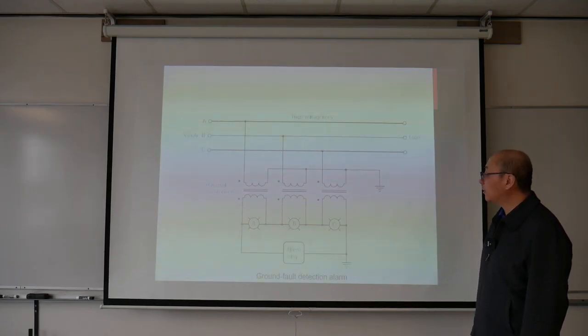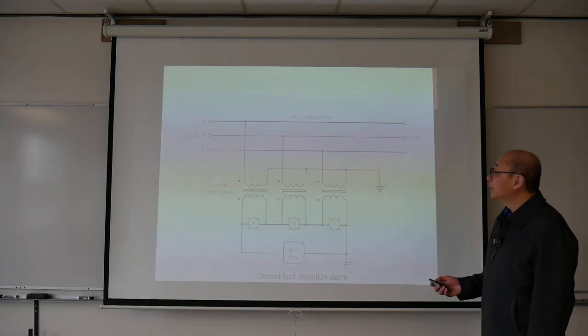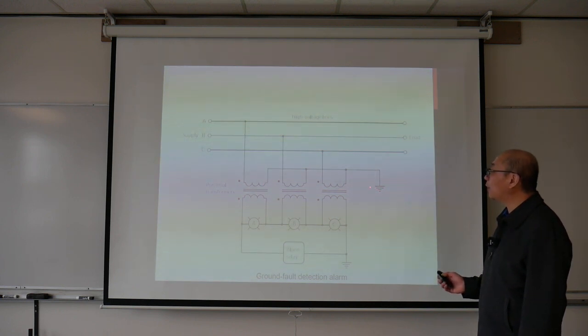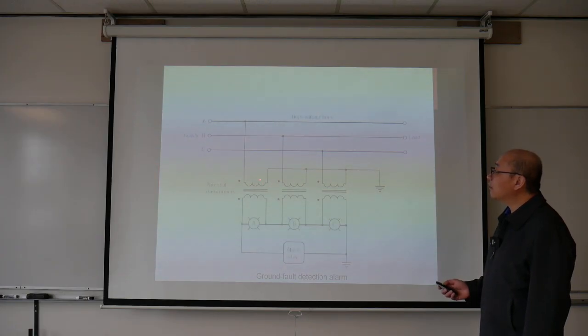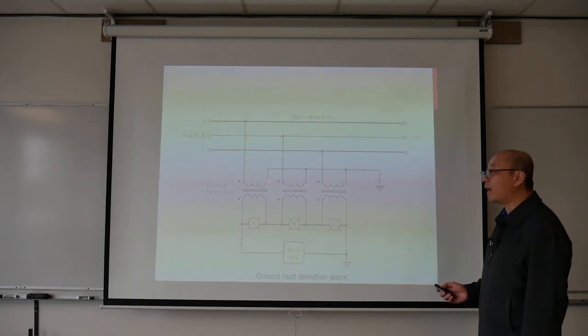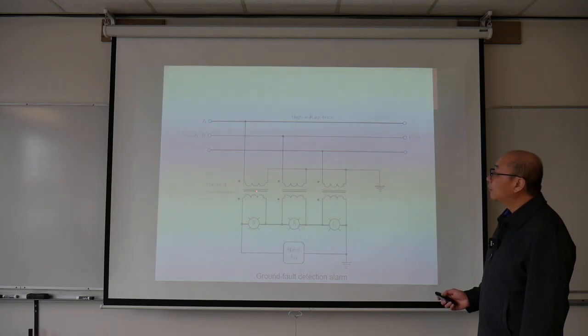So here is the circuit with the ground fault alarm relay in there. The primary of the three potential transformers is in a Y connection. The common point is connected to ground. So when there is no ground fault in the circuit, all three potential transformers on the primary side reduce the line voltage to the phase voltage in the Y system. The secondary side of those three potential transformers is delta connected, and each lamp is connected across the secondary terminals of each potential transformer. So when everything is working normally, all three potential transformers have a voltage drop across them and produce a secondary voltage. The three lamps come on with an equal amount of voltage, so they come on at a certain amount of brightness.